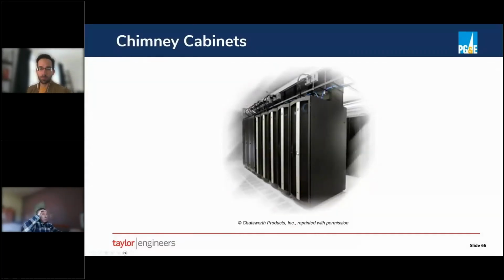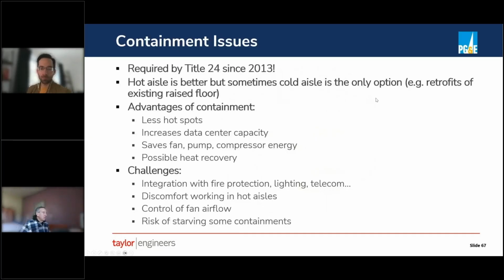Another form of containment is a chimney rack. So instead of using walls and doors to block off your hot aisle or your cold aisle, you can simply have a rack that's a little bit deeper than a standard rack. And the back of the rack is basically sort of a return duct that can then just be ducted up into your ceiling, right? And so there's no way for the air to go out of the rack and back into the front of another rack or server. It's all being collected and basically ducted to your ceiling, which goes back to your area. Containment has been required in Title 24 since 2013, so more than 10 years now.